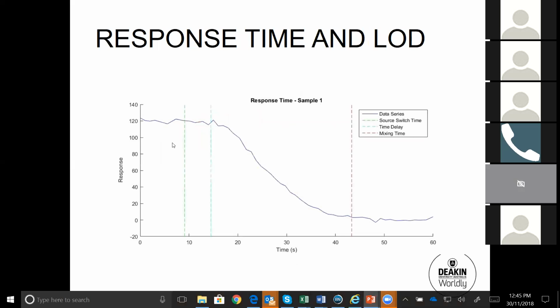This is response time. This is a very important metric when we talk about the utilization of this instrument for field measurements. So we tested response time and also time delay, because we have two fractions. We have particles and gas phase. We are testing the oxidative potential of the gas phase by placing a filter in front of the stream.